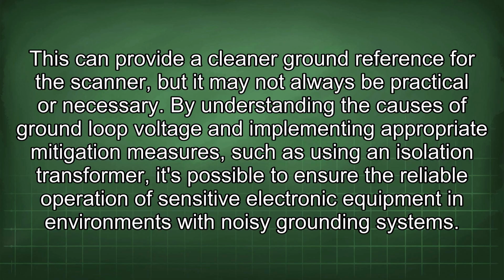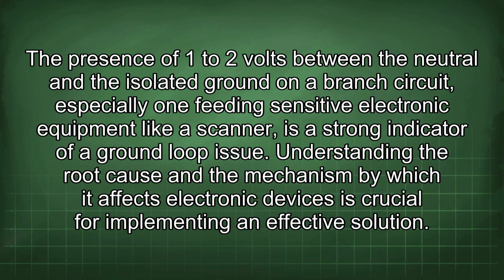By understanding the causes of ground loop voltage and implementing appropriate mitigation measures, such as using an isolation transformer, it's possible to ensure the reliable operation of sensitive electronic equipment in environments with noisy grounding systems. The presence of 1 to 2 volts between the neutral and the isolated ground on a branch circuit, especially one feeding sensitive electronic equipment like a scanner, is a strong indicator of a ground loop issue.